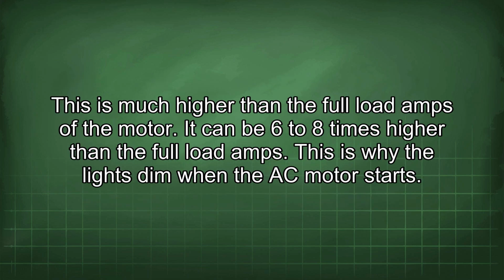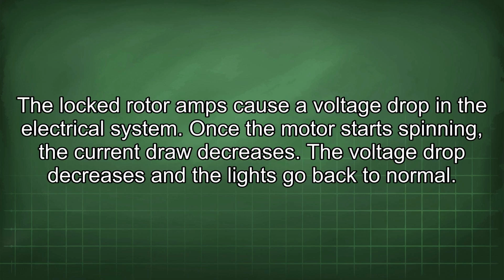This is much higher than the full load amps of the motor. It can be 6 to 8 times higher than the full load amps. This is why the lights dim when the AC motor starts. The locked rotor amps cause a voltage drop in the electrical system. Once the motor starts spinning, the current draw decreases. The voltage drop decreases and the lights go back to normal.